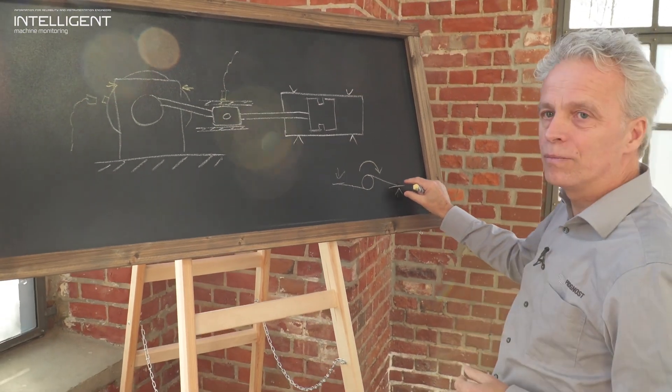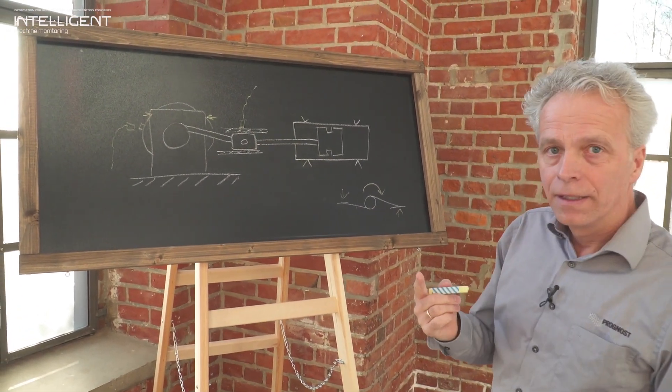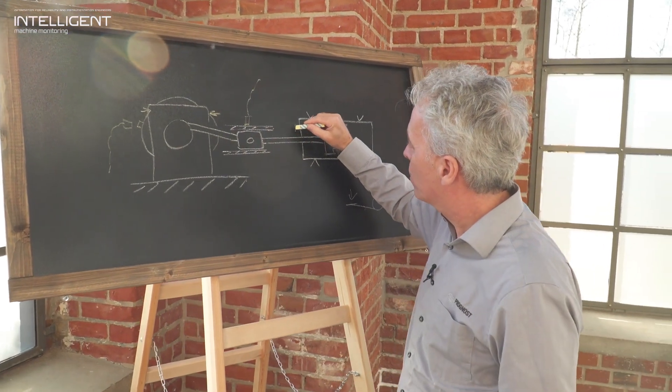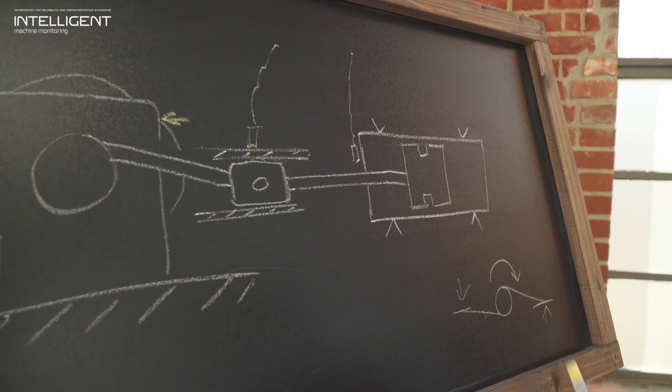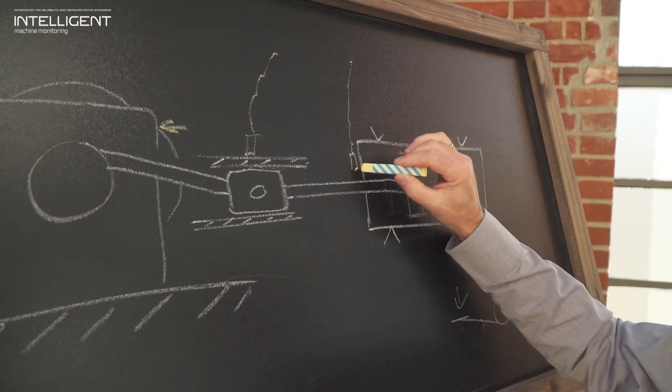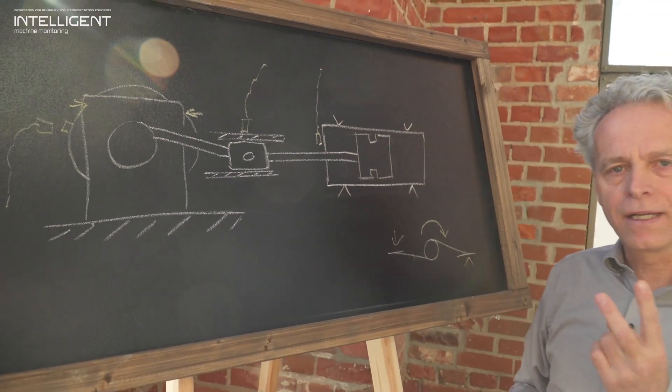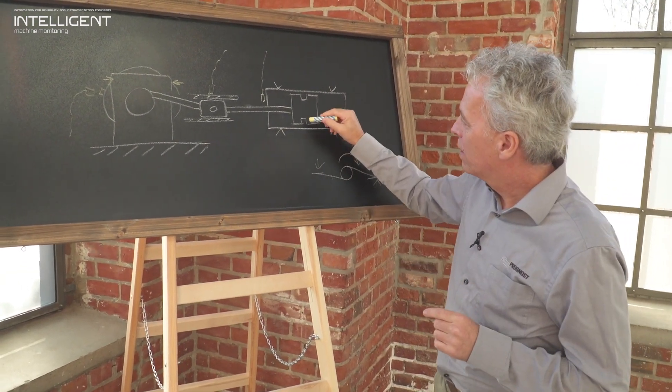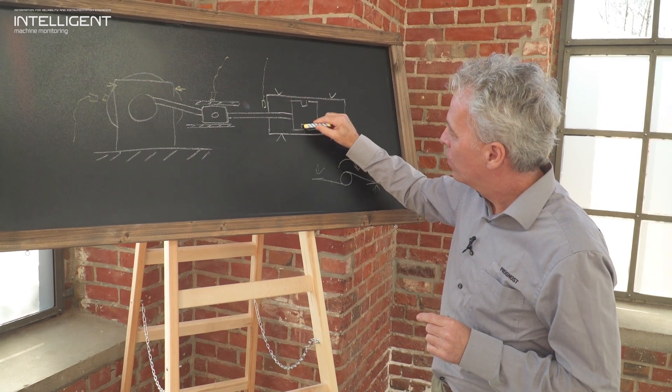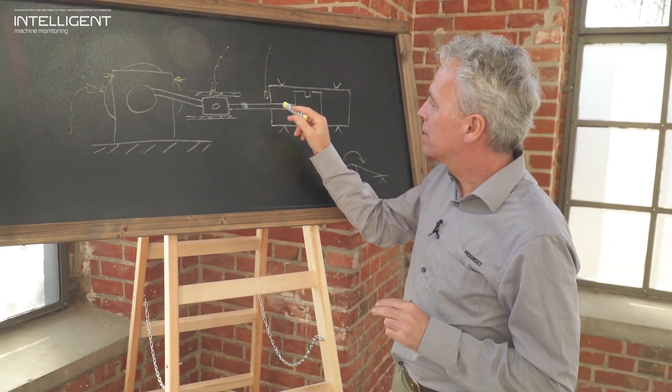At the packing we install a proximity sensor. This proximity sensor measures the distance between the sensor tip and the piston rod, and usually two different analyses are carried out based on the signal. One is the wear of the rider bands, number two is related to the machine protection.